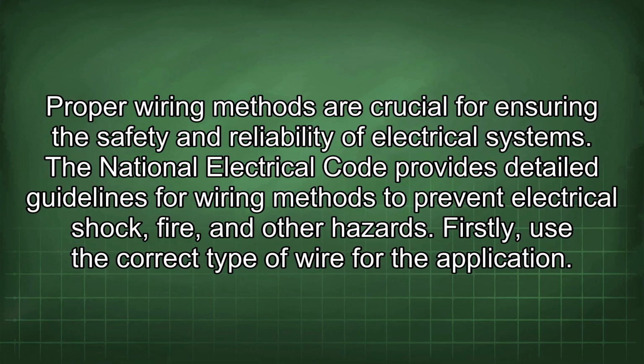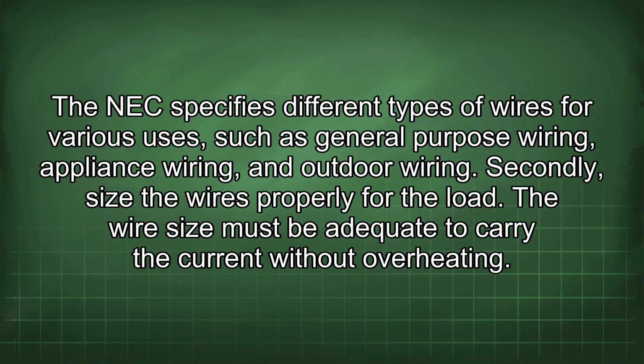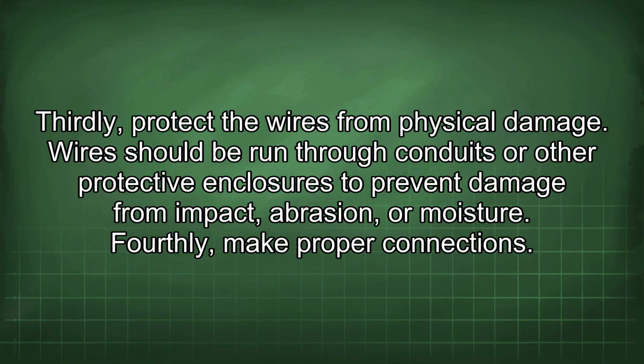Firstly, use the correct type of wire for the application. The NEC specifies different types of wires for various uses, such as general-purpose wiring, appliance wiring, and outdoor wiring. Secondly, size the wires properly for the load. The wire size must be adequate to carry the current without overheating. Thirdly, protect the wires from physical damage. Wires should be run through conduits or other protective enclosures to prevent damage from impact, abrasion, or moisture.